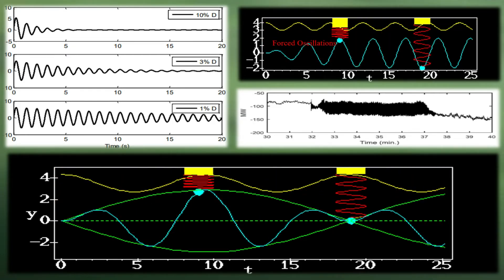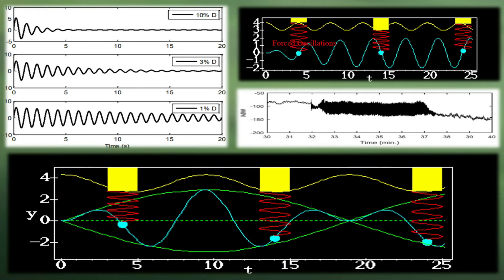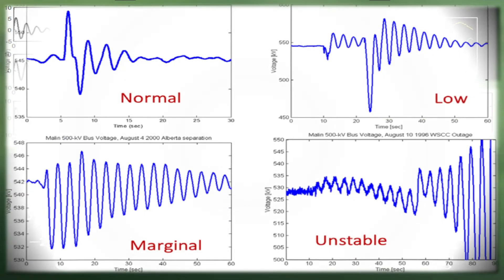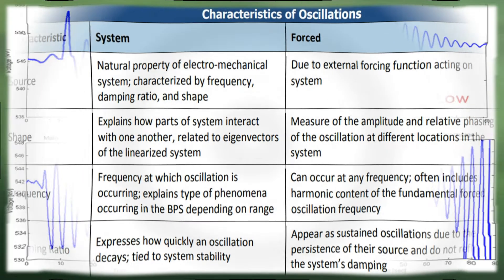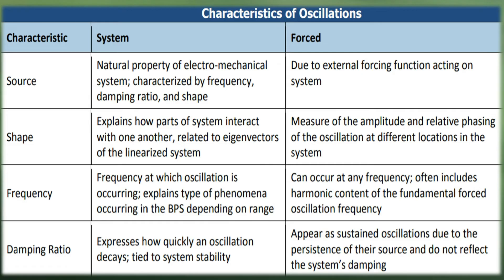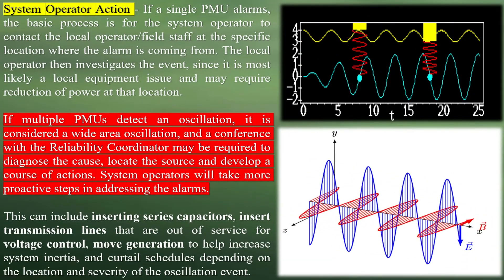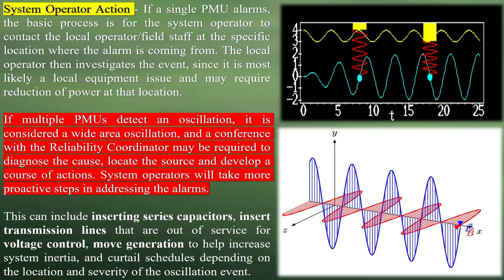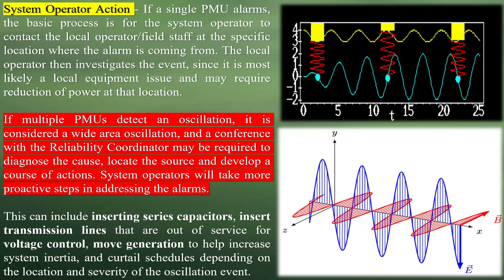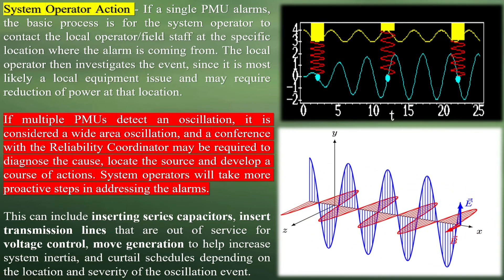System operator action: if a single PMU alarms, the basic process is for the system operator to contact the local operator or field staff at the specific location where the alarm is coming from. The local operator then investigates the event, since it is most likely a local equipment issue and may require reduction of power at that location. If multiple PMUs detect an oscillation, it is considered a wide area oscillation, and a conference with the reliability coordinator may be required to diagnose the cause, locate the source, and develop a course of actions.